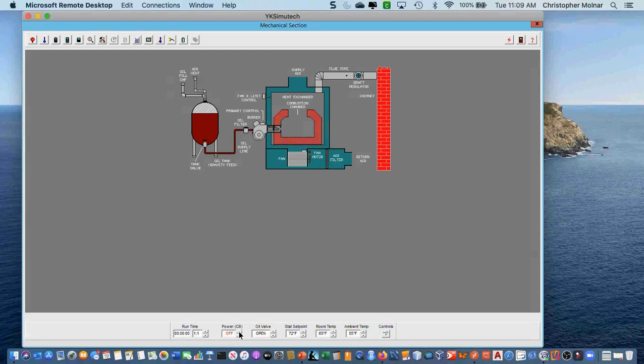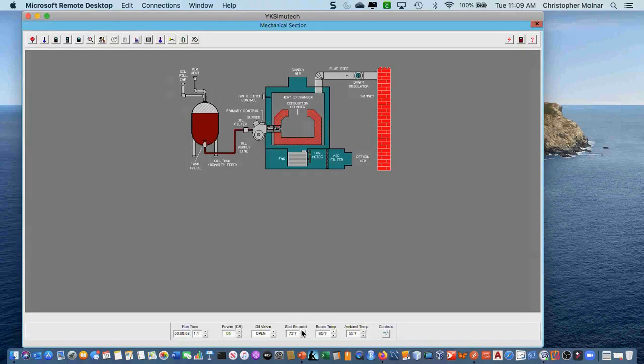Okay, you're going to turn the power on. Oil valve is open. We'll turn the stat set point way up. Okay, we'll turn the thermostat set point up. System comes on. We have flame. That's our normal operating procedure.